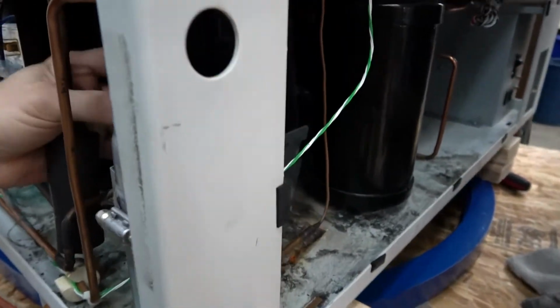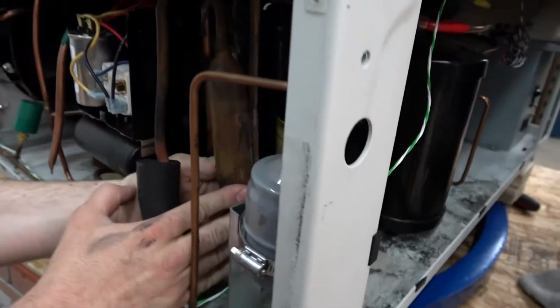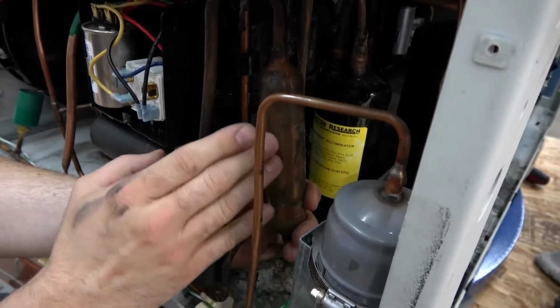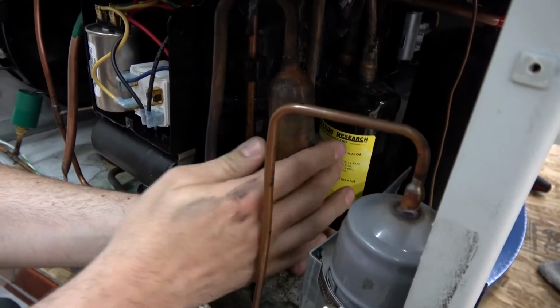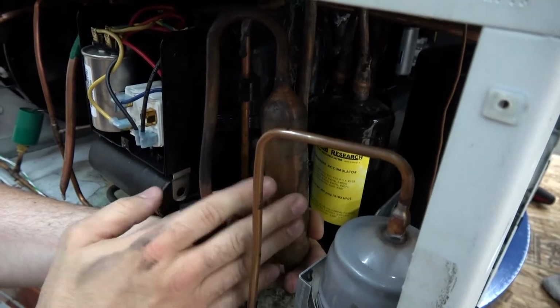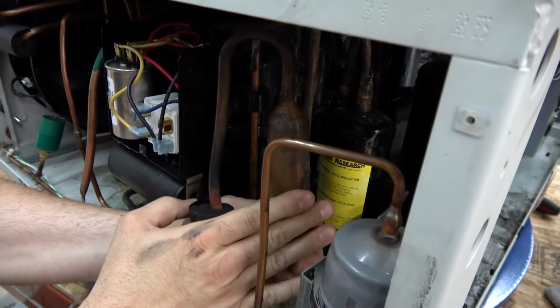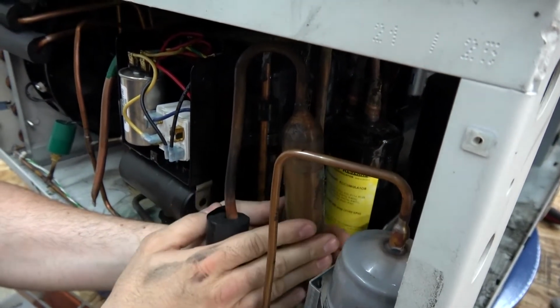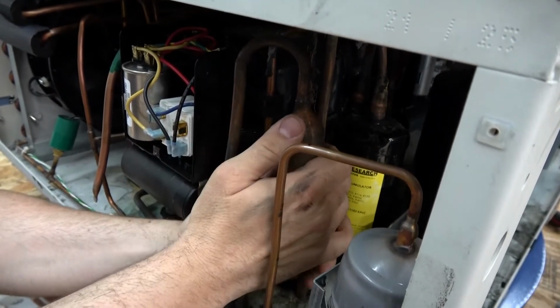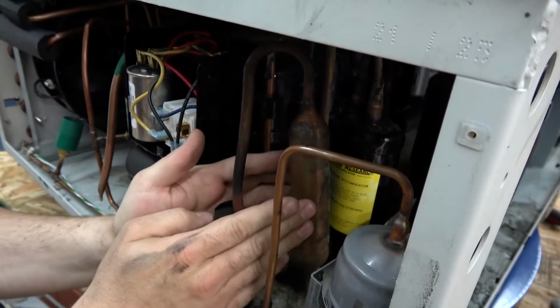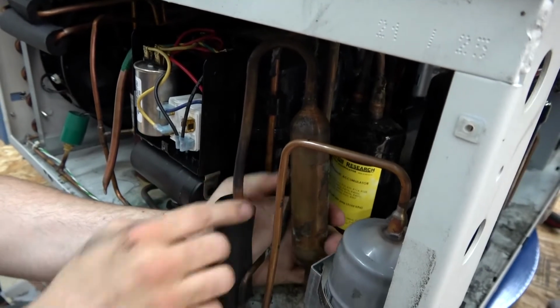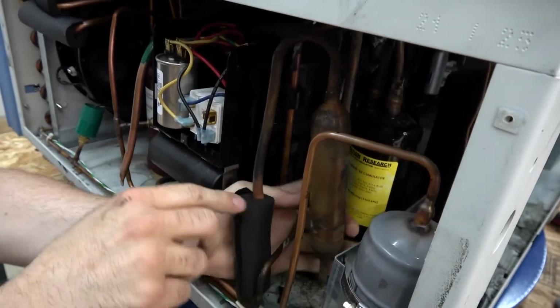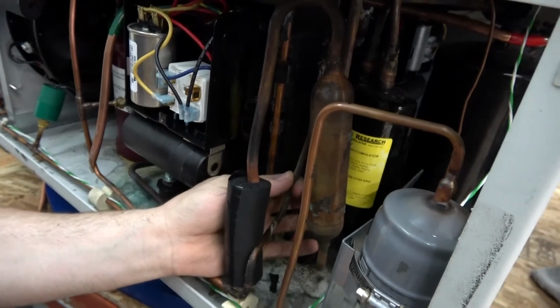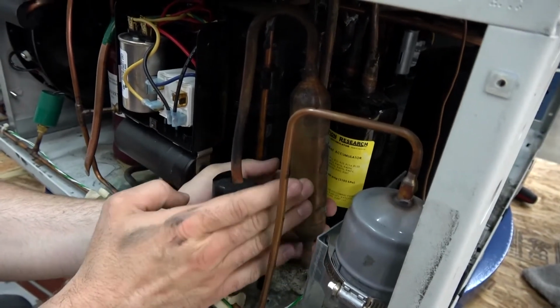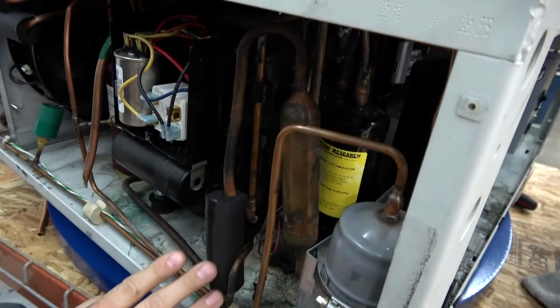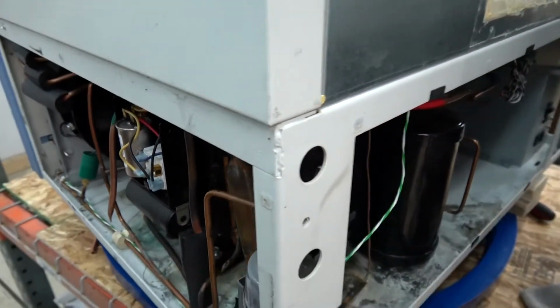It comes up, and also, interesting little thing, it touches this component. This is another one of those expansion tanks we talked about. This is the return from the second stage after it's done up here. It uses some more of its cooling capacity to cool off this line when it's coming up and to heat this up. So basically, this component takes heat from this line, which helps cool this off, which is what we want to do, and which helps heat this up because we want to make sure there's no liquid, remember, getting back in the compressor. So it's kind of a twofold thing there.